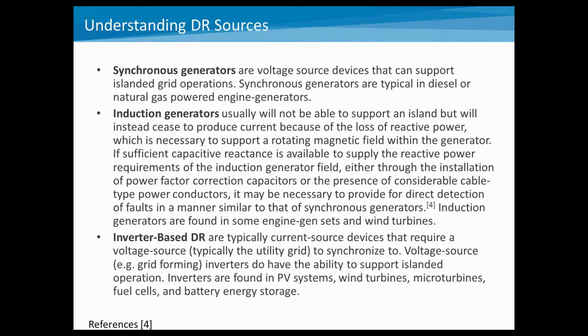And then finally, inverter-based distributed resources. This is something that's becoming much more prominent with things like photovoltaic systems or energy storage systems, where you have an inverter-based system. Now, typically, in general, you need a grid-forming inverter to provide that support, so a voltage source based inverter system. A lot of times now, these inverters are operating in a current control mode, and so they aren't necessarily able to provide a voltage source, but are phase locked into the AC power system.